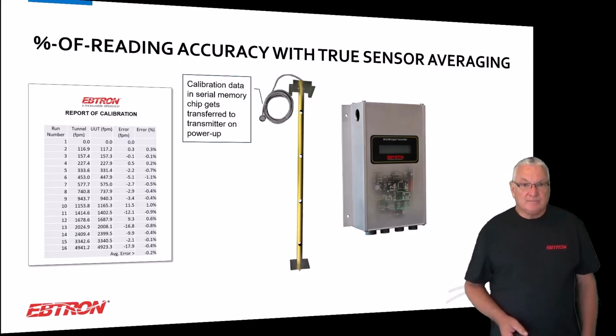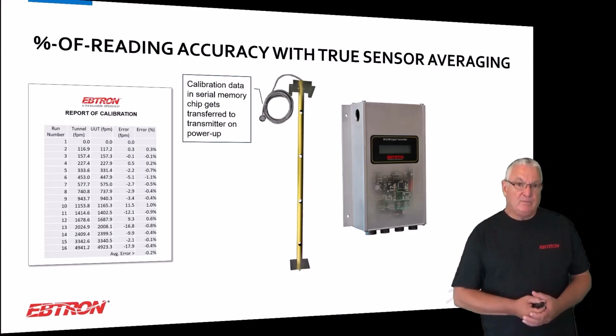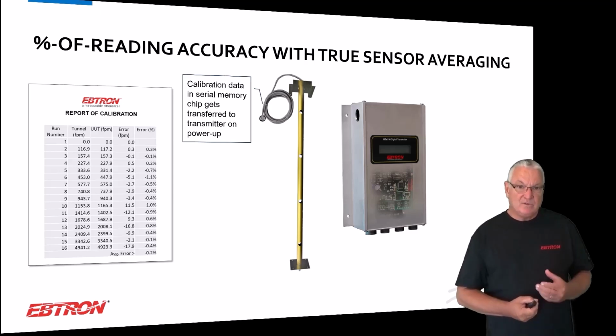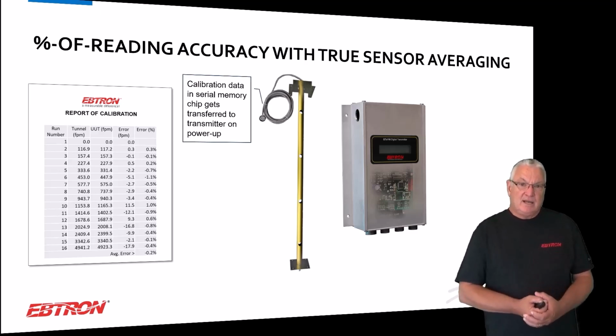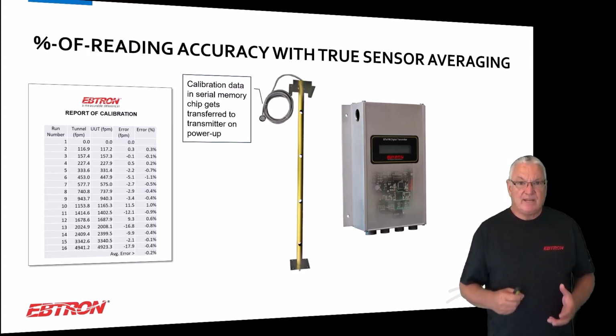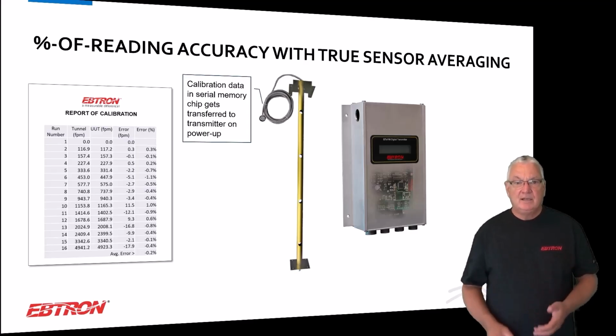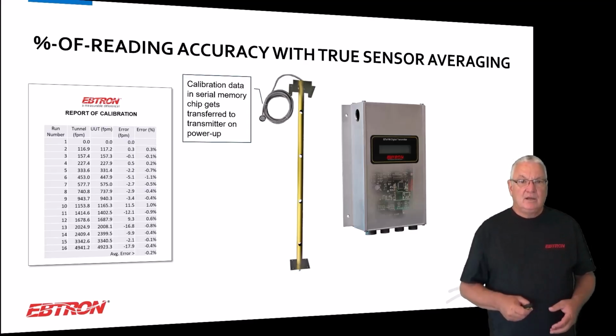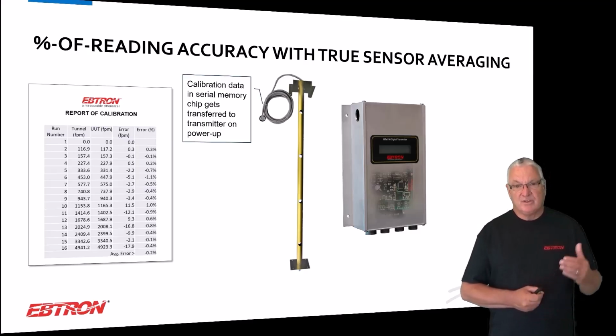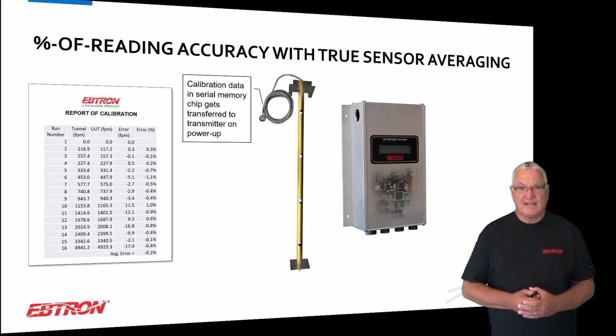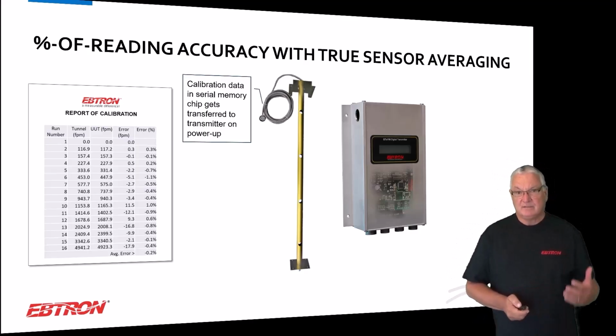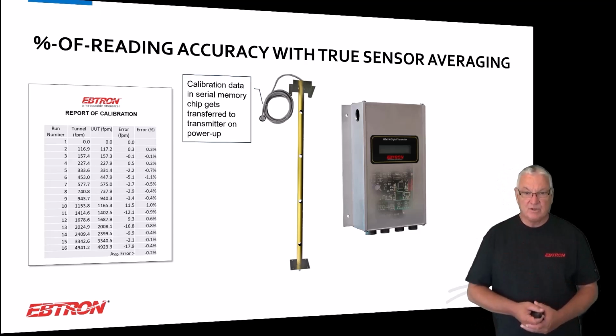Each individual, this is a probe again, basically the sensors are very variable. They all have to be calibrated. And if you ever look at one of these tubes, you'll see that there's barcodes on each sensor node. It's because in the manufacturing process, we have to retrieve all that calibration data and we have to store it in a serial memory chip at the connector of each one of these probes so that when you plug it into the transmitter, all of that calibration data is transferred to the transmitter. It doesn't matter what model unit that we're doing.